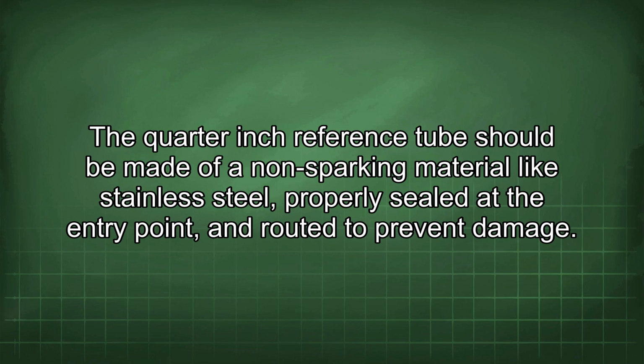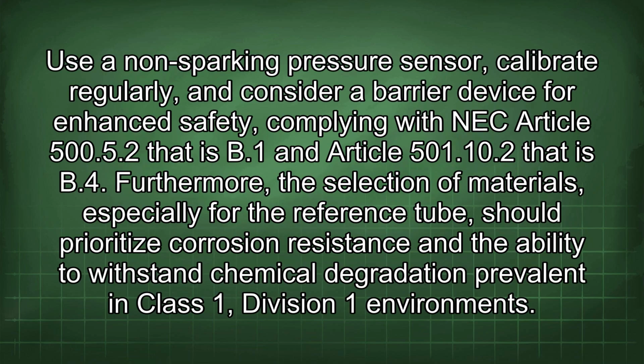The quarter-inch reference tube should be made of a non-sparking material like stainless steel, properly sealed at the entry point, and routed to prevent damage. Use a non-sparking pressure sensor, calibrate regularly, and consider a barrier device for enhanced safety, complying with NEC Article 500.5(2), that is B1, and Article 501.10(2), that is B4.